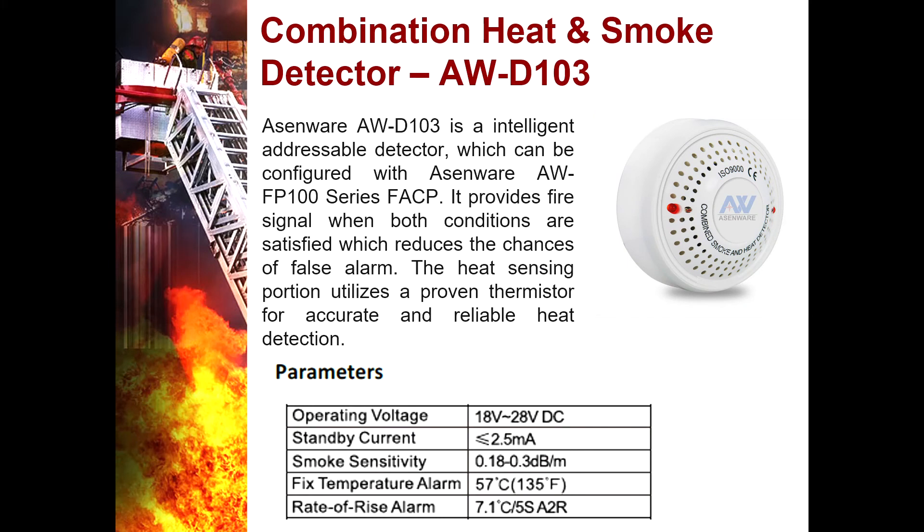Combination Heat and Smoke Detector AWD103 — it is an intelligent addressable detector which can be configured with the Asenware AW-FP100 series. It provides a fire signal when both heat and smoke conditions are satisfied, reducing the chances of false alarms. The sensing portion utilizes a proven thermistor for accurate, reliable heat detection. It has a smoke sensitivity of 0.18 to 0.3 decibels per meter, a fixed temperature alarm of 57 degrees Celsius, and a rate-of-rise alarm of 7.1 degrees Celsius per 5 seconds.